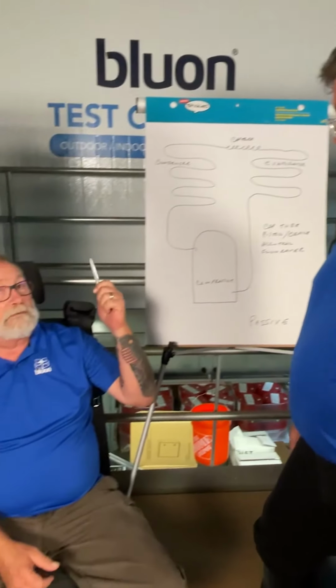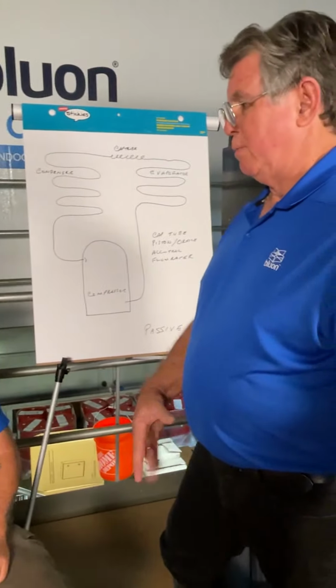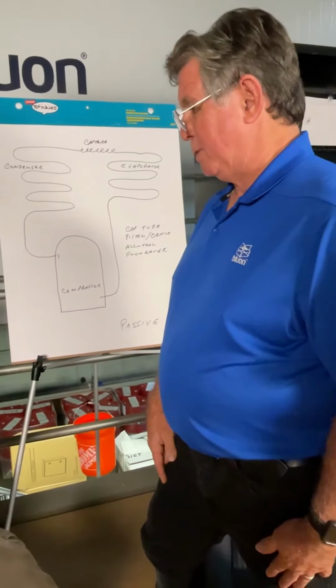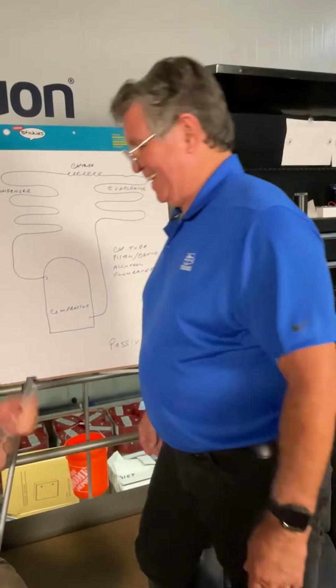And the other thing that they built into it is when you open up that calculator, it has your safety built into it. You're going to see numbers for your target already. So if you don't fill anything out, it's going to have a 5 as the minimum superheat. We don't want you guys to blow up compressors. Because we're not compressor manufacturers, so we don't make anything when they blow up. So it's just a safety built in.